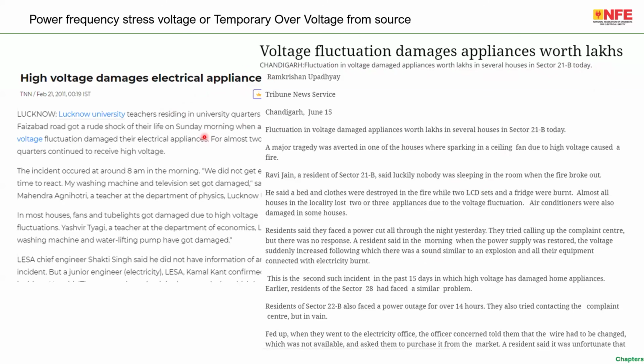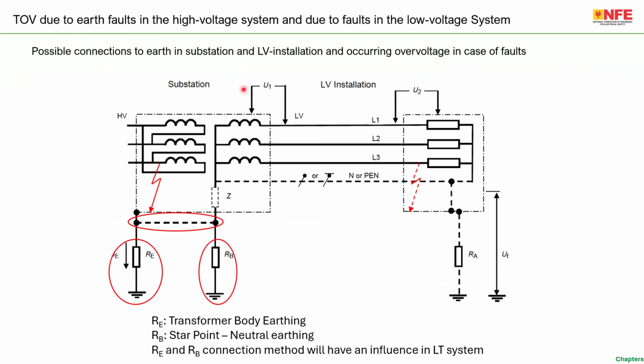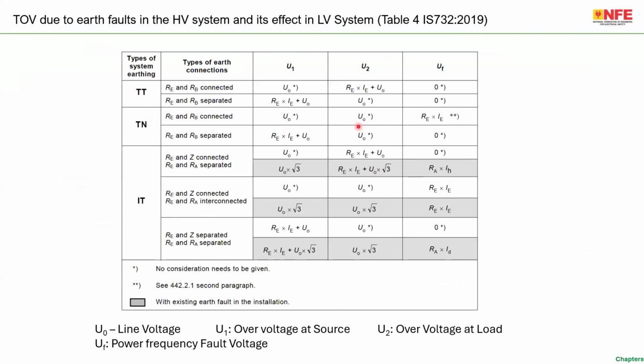For example, a fault on the HV side of a transformer, maybe the surge arrestor failed. At the same time, maybe in hundreds of houses the LED TV is gone, or electrical appliances are failing. The refrigerator is burning, the inverter is burning. Such failures are due to the transfer of potential from the high voltage side of the transformer to the low voltage side of the transformer. Now the regulation as well as the standards set limits. For example, the maximum limits in the standard are explained in IS 732 clause 4.5. You can find this kind of a picture. You can find the calculations again in a table.